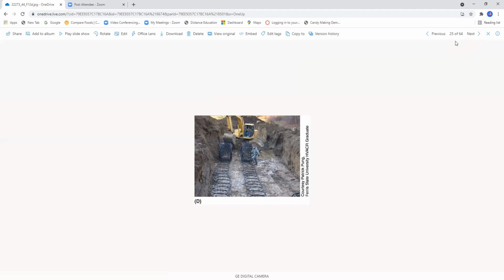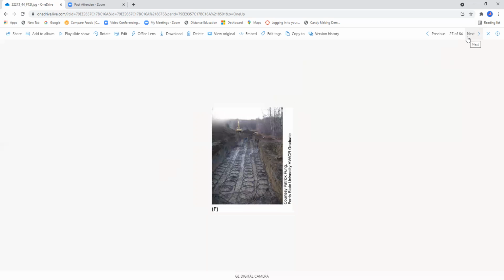Okay, in this situation here, this is letter D. Basically, he's in the process of rolling out these Slinky groundwater loops. In this picture here, the technician is rolling out the last of the 4 Slinky ground loops here. So you can see how they look like Slinkies now laid down flat. Quite interesting. But look at all the earth that has to be moved in order for this to be put in. It's an expensive process, I can tell. Okay, and in this illustration, 44.12, the freshly excavated trench showing 4 Slinky ground loops with a large backhoe in the background.